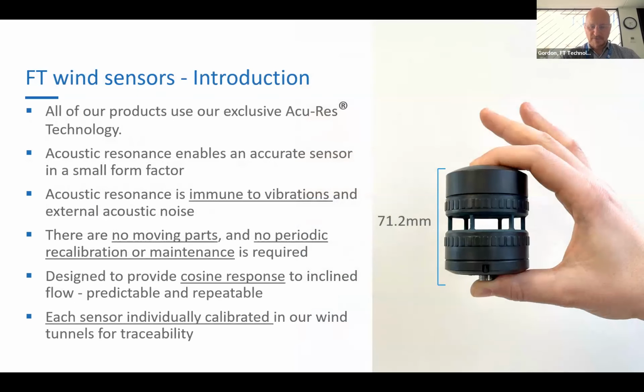So what makes us different? You've probably seen ultrasonic wind sensors somewhere. They all work off a technology called time of flight, which basically uses the Doppler effect to measure the transit time of an acoustic pulse from one transducer to another. That's great technology, but it can be prone to vibration. Under very heavy vibration, those path lengths can change and pollute the measurements, affecting the accuracy of the sensor. Now, what our sensor uses is a technology called acoustic resonance.